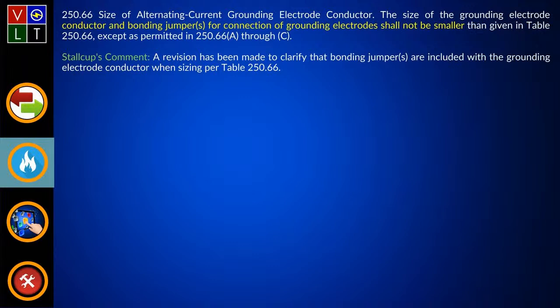We've had this argument before, and I think there's going to have to be a little more change on this, because if you go back and look at 1978, '81, '84, in those areas there, when they first started developing what at that time was table 250-94, the code making panel made it very clear. If I was going to a ground or to a concrete encased electrode, they said that even somebody had made a proposal and said they thought it was an oversight, because before they started making changes to that table, you could actually use the table and go smaller than a number 4.